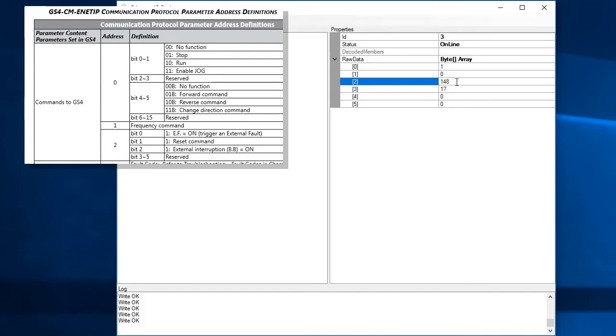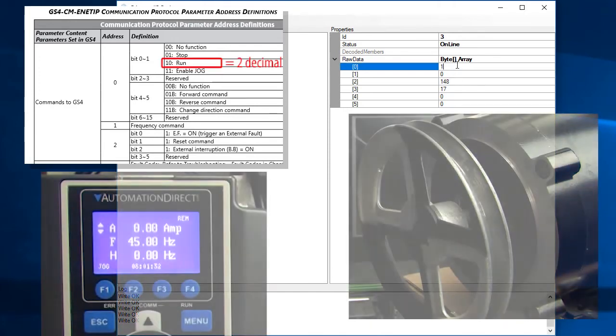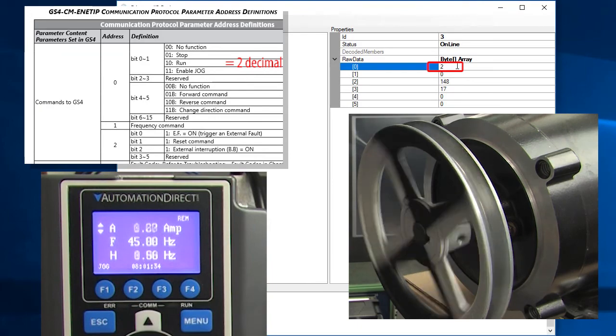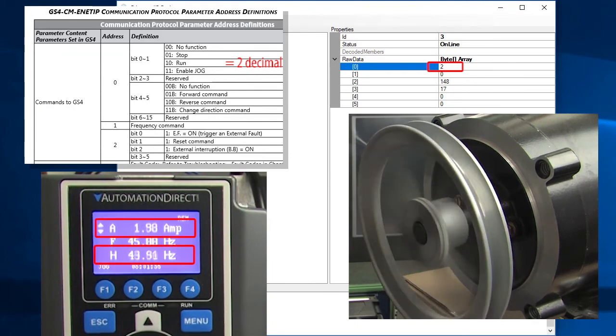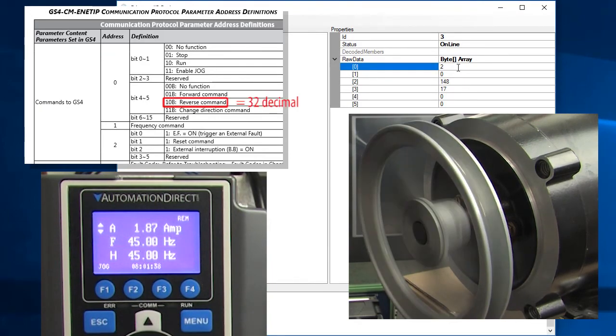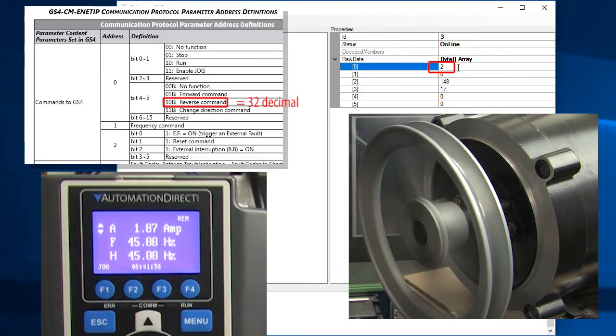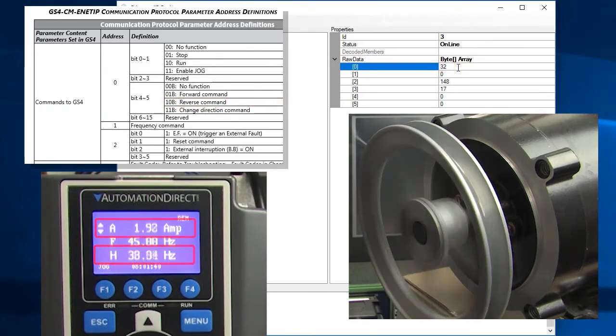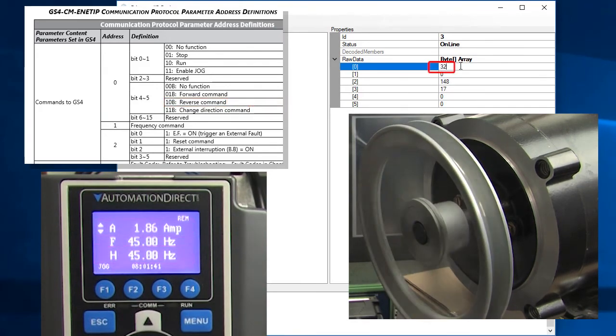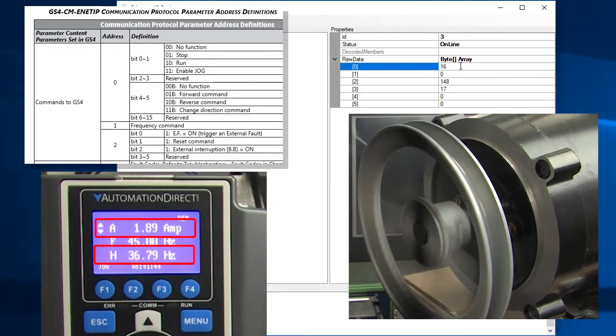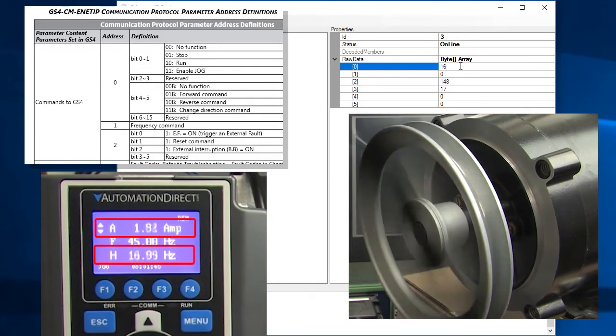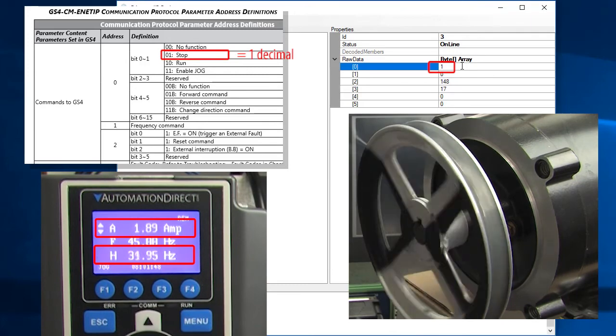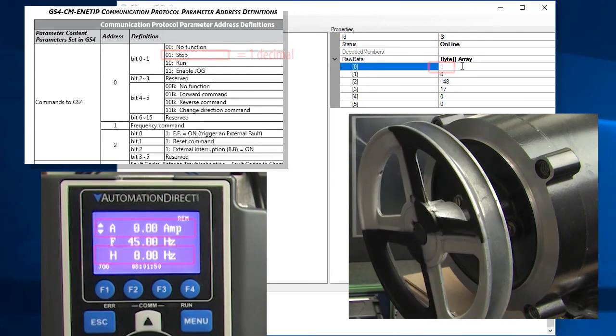The buffer definition table also says if we set this bit in the first word – which is a decimal 2 – the drive should start running. And sure enough it does. It says if we set bit 5 – which is a decimal 32 – the drive should reverse direction. And it does. Set bit 4 – which is a 16 decimal and the drive goes back to forward. Set bit 0 and the drive stops. Perfect.